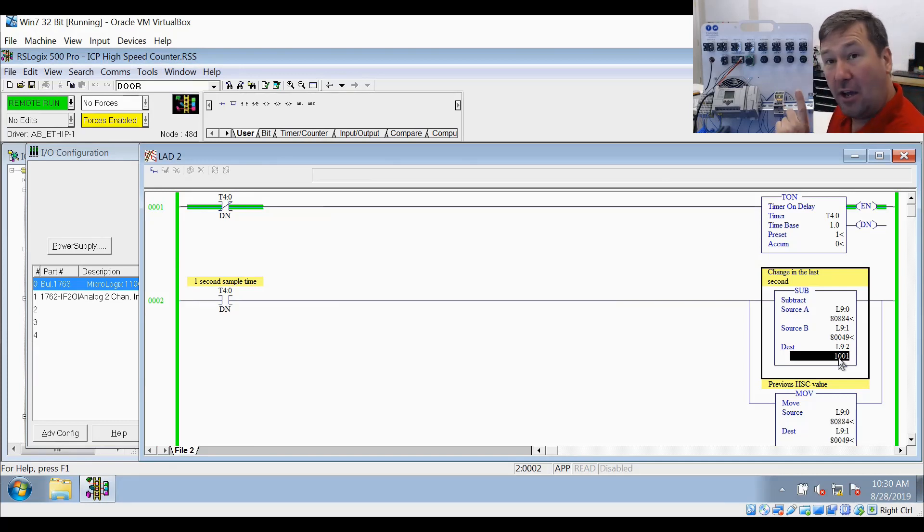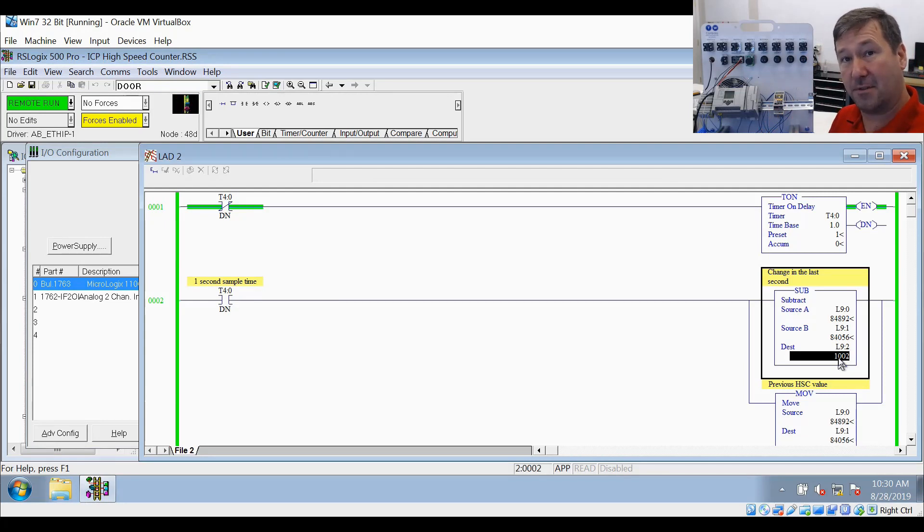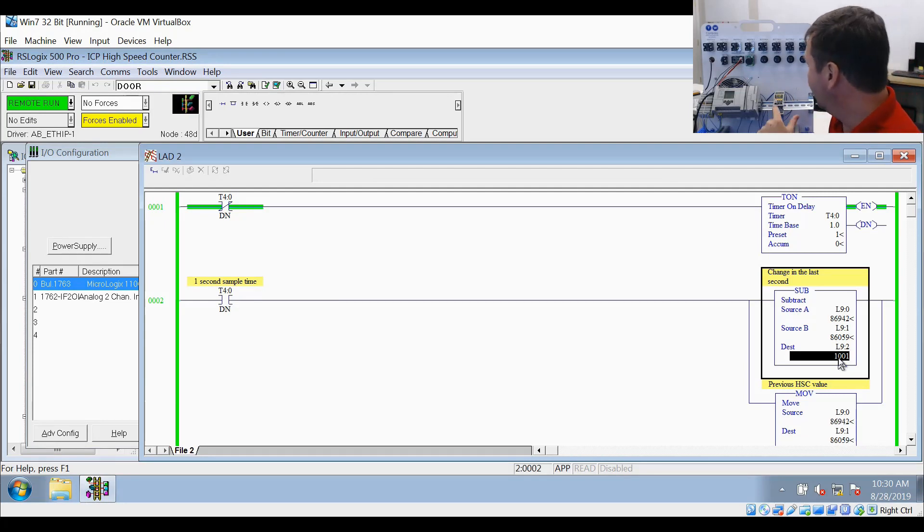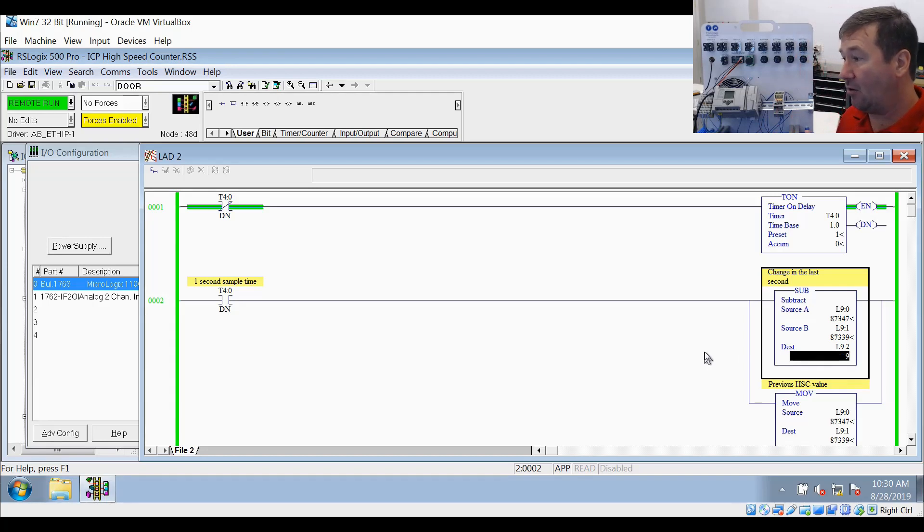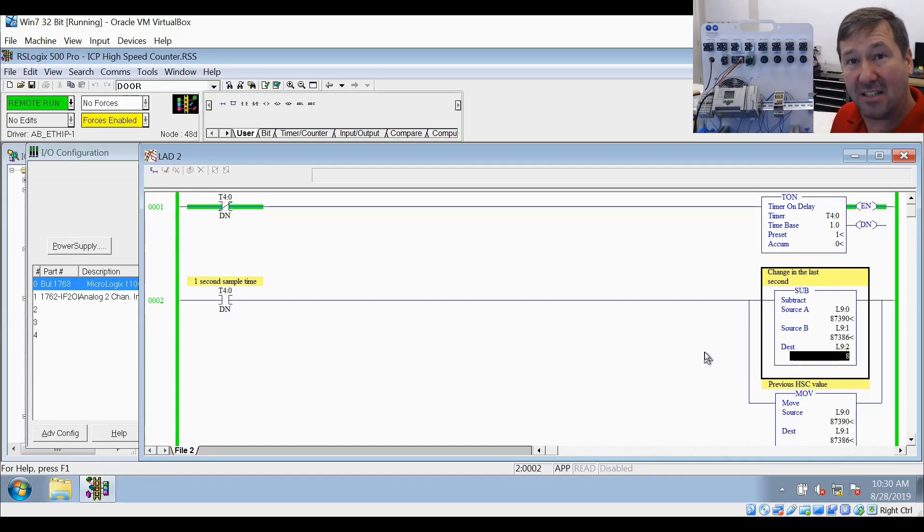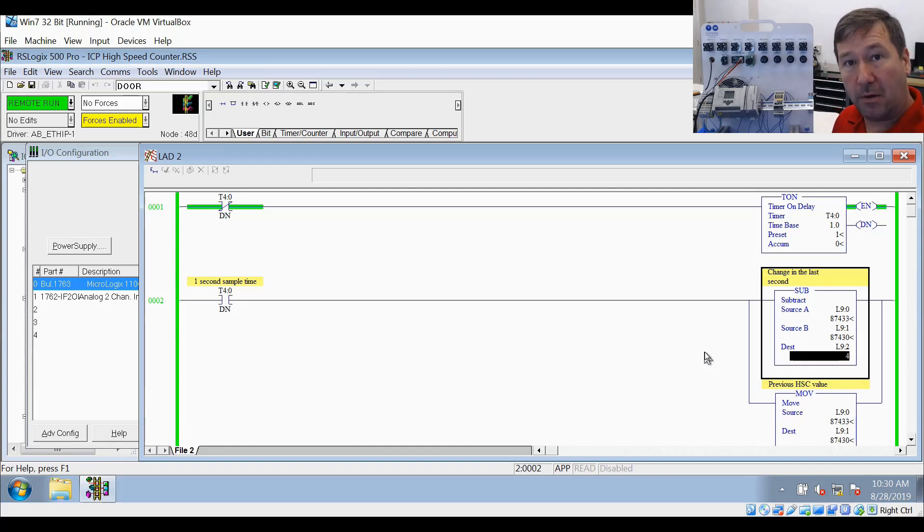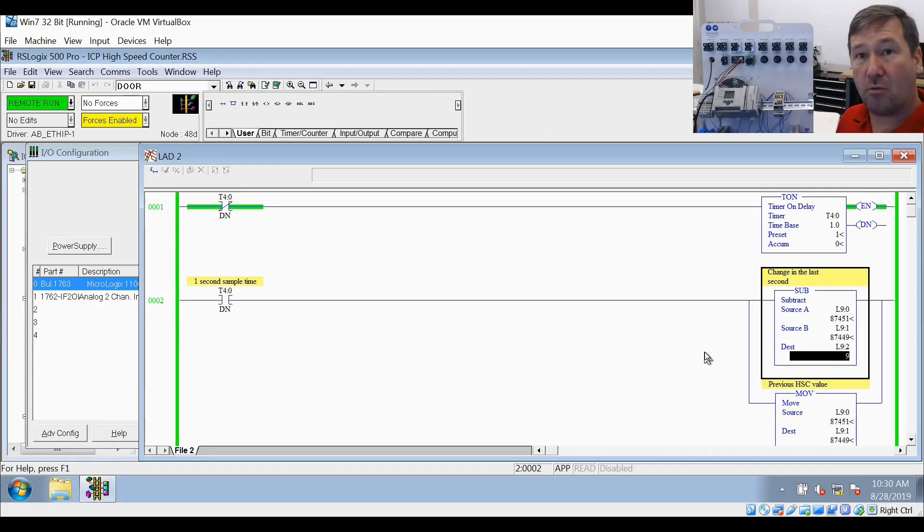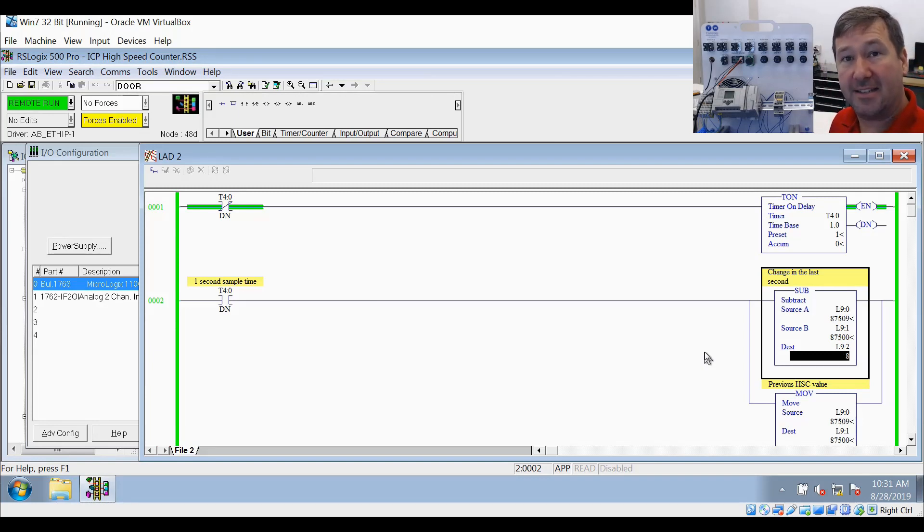Now let's go to 10,000 hertz, which is 10,000 pulses per second. It's a lot of pulses going through there. And now, look, we're dropping back down to 11 pulses. This is what I see. People are calling saying, 'Hey, this worked when we were running it slow, but as we start ramping it up, we're having trouble.' Well, this is why. It is this input filter here.